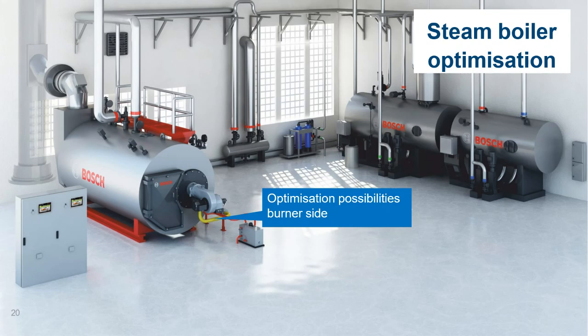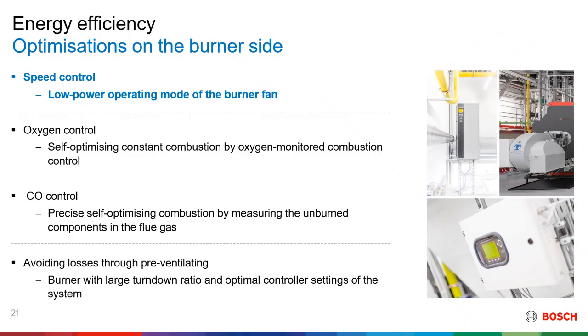Okay. Then the second part of efficient steam generation will be how do you optimize the burner side. Okay. Nick, you can go to the next slide. Okay. So on the burner side, there are three main areas of optimization. The first one being speed control, the second section being the flue gas side, it's O2 control or oxygen control, CO control, and then the last part being purging during burner startups. Okay. Next slide.